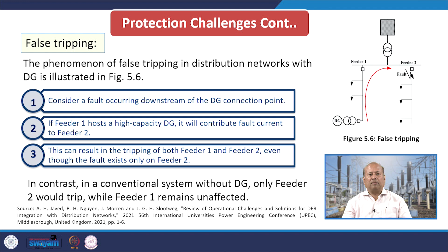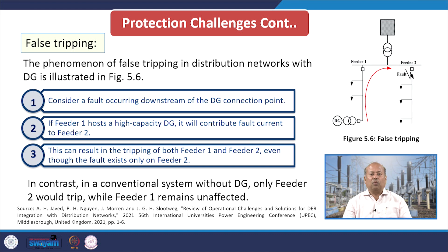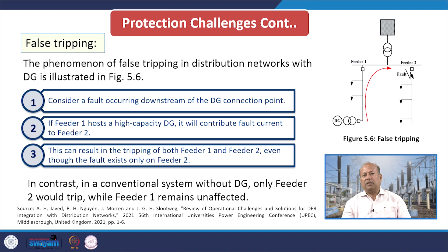Regarding false tripping, as seen from diagram 5.6: it considers a fault current downstream of the DG connection point. If feeder 1 hosts a high capacity DG, it will contribute fault current to feeder 2. This can result in the tripping of both feeder 1 and feeder 2 even though the fault exists only on feeder 2. In a conventional system without DG, only feeder 2 would trip while feeder 1 remains unaffected — this is how false tripping may happen due to DG integration.